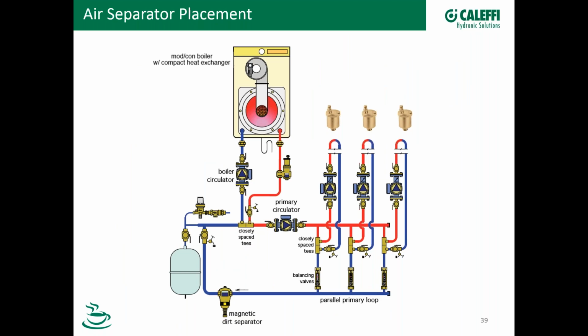And a mod con. This is a nice picture. I like it because here's a vertical air separator. We have closely spaced T's, which is really common, and we have a primary circulator here. So this circulator is pumping water in this loop right here, and we show a dirt separator down here, a magnetic dirt separator. That's another webinar. But again, we have air separation here, and then we're going to have air venting out here at any other high points. So I'm thinking you're getting the message by now.